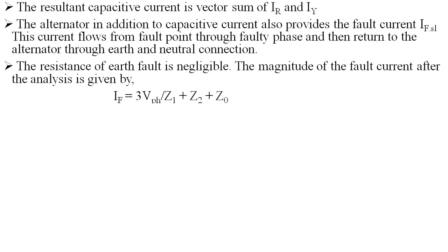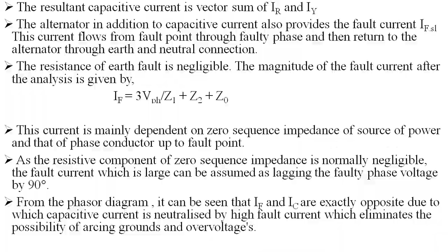Okay, and this current is mainly dependent on the zero sequence impedance of the source of the power and that of the phase conductor up to the fault point. As the resistive component of zero sequence impedance is normally negligible, the fault current, which is large, can be assumed as lagging the faulty phase voltage by 90 degrees. So from the phasor diagram, it can be seen that the fault current and the capacitive currents are exactly opposite, due to which the capacitive current is neutralized by the high fault current, which eliminates the possibility of arcing grounds and overvoltages.